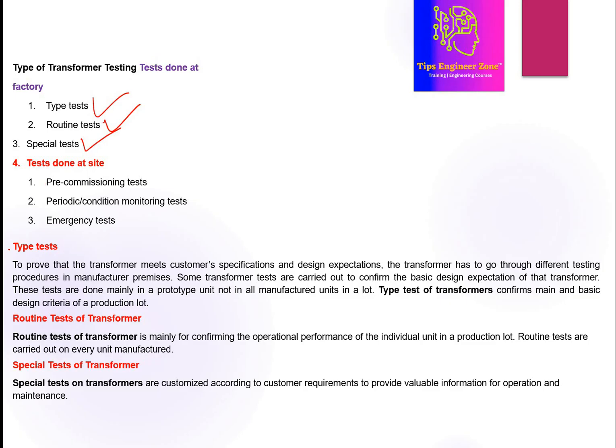A type test is a test to prove that the transformer meets customer specifications and design expectations. The transformer has to go through different testing procedures on the manufacturer's premises, and some tests are carried out to confirm the basic design expectation of the transformer. These tests are done mainly on a prototype unit, not on all manufactured units in a lot. Only prototype units, only selected units.